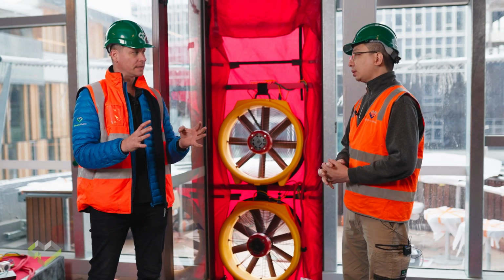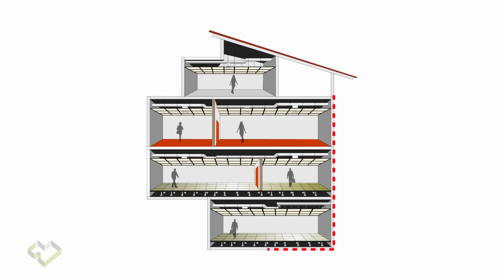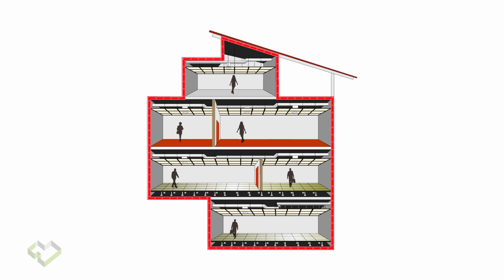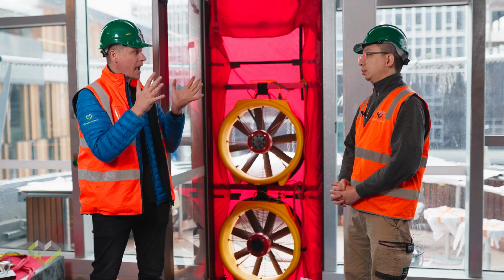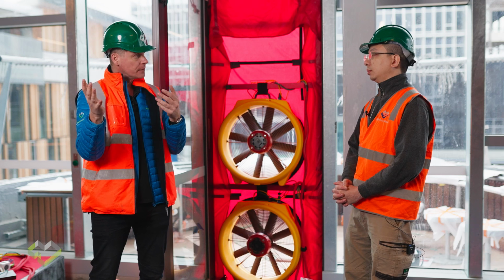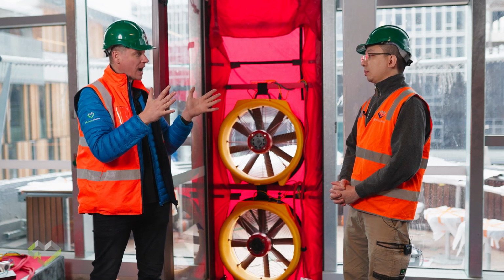And a permeability rate means that per every square metre of building envelope, that's the ground floor of the building, all of the facades and the roof, how much each square metre is leaking per hour. What that enables us to do is compare apples with apples of other buildings on how leaky they are.